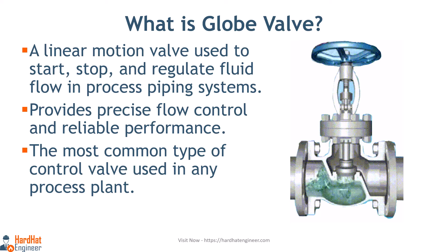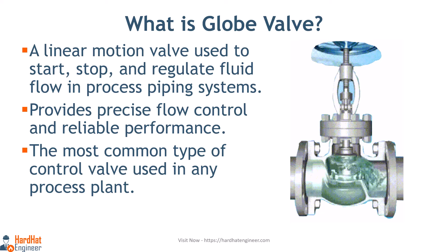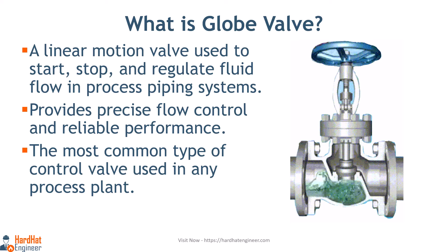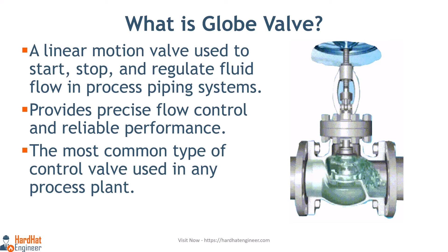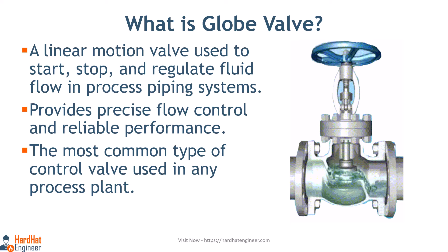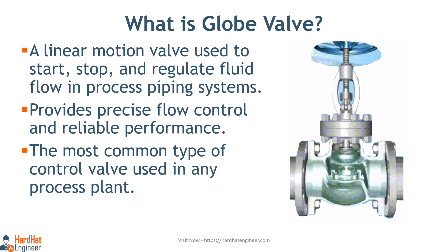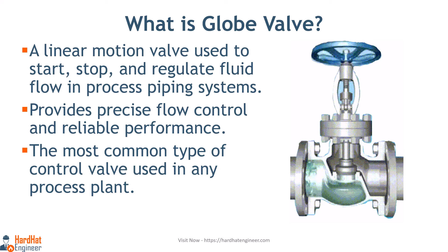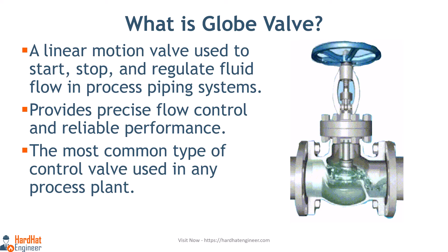What is a globe valve? A globe valve is a linear motion valve used to start, stop, and regulate fluid flow in process piping systems. It is a control valve that provides precise flow control and reliable performance. During opening and closing, the disc moves perpendicularly to the seat. This movement creates an annular space between the disc and seat ring that gradually closes as the valve closes.